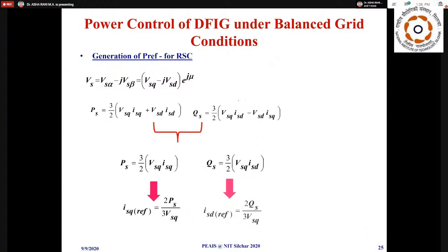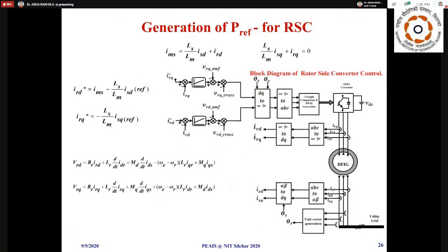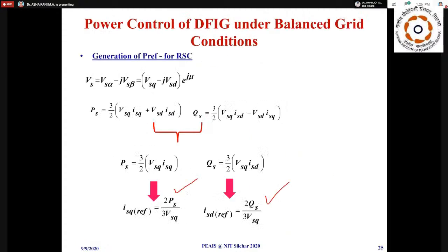One thing I have to tell you, generally, you have seen the kind of power control I told you earlier. In the case of power control, we generate reference currents from P and Q by dividing with the voltage. These currents are fed to the control loop such that, if I'm setting I want to pump 1 megawatt power and don't want any reactive power taken from the grid, I'll put this as 0 var. If I want to pump 1 megawatt from the machine, I will put this PS as 1 megawatt.